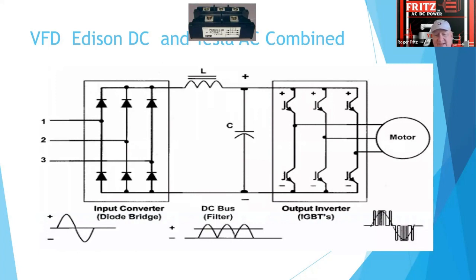So what happens is we take this AC power, it rectifies it here and gives us these ripple voltages here. Then they put filter capacitors across here on the bus circuit and literally smooth that out, because you want very clean DC before you give it to the transistors to rebuild the output. And then this is a 6-pulse transistor type output. It literally builds pulses in here to rebuild the sine waves.